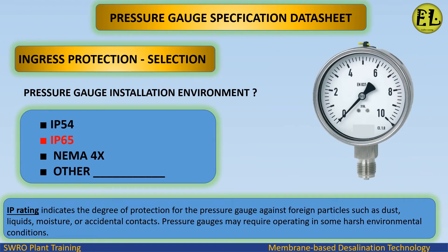Ingress protection selection based on the pressure gauge installation environment. Available ratings include IP54, IP65, and NEMA 4X. The IP rating indicates the degree of protection against foreign particles such as dust, liquids, moisture, or accidental contact, as pressure gauges may need to operate in harsh environmental conditions. We select IP65 for this application.